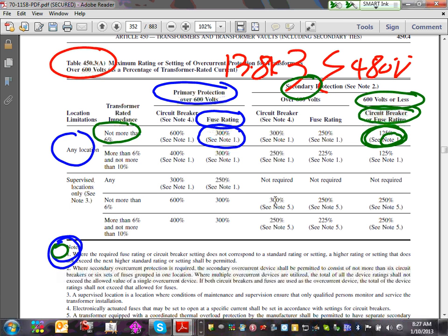No, you go down here. More than 6. More than 10? Then you have to follow the manufacturer's instructions. Typically, more than 10 is high impedance. You know what high impedance means? You have voltage drop problems and losses. So these are typical values. If you have different values for whatever application they use, then you have different rules.